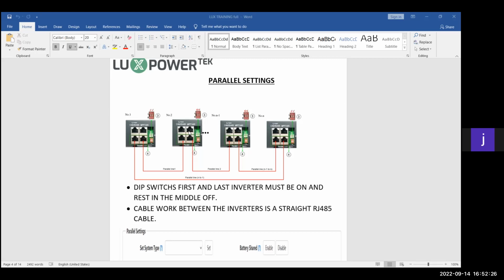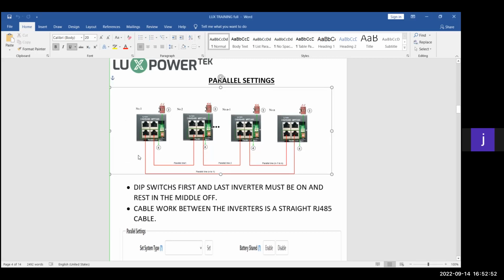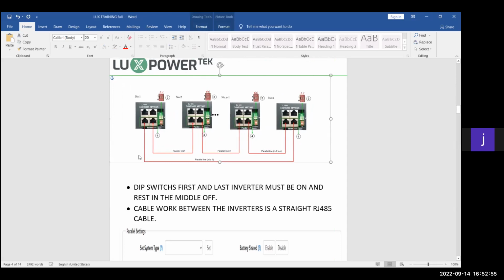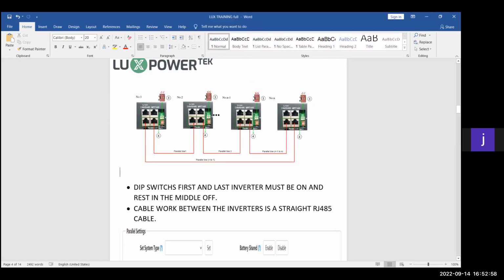If there's one inverter, then it doesn't matter where these dip switches are, your inverter will function normally. So if it's one inverter, it can be up or down. I usually tell the clients to leave it in the down position. That's how it comes out of the factory, but it doesn't matter if there's one inverter. But as soon as there's more than one, communication wise in a parallel system, this only assigns the first and the last inverter, so the system knows which inverters have this specific communication chain on them. That's basically all that this dip switch is designed for: to tell the inverters you are first and you are last, and all the ones between you are in your communication chain.